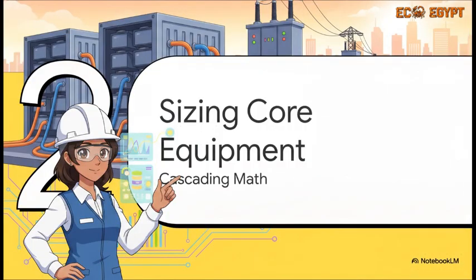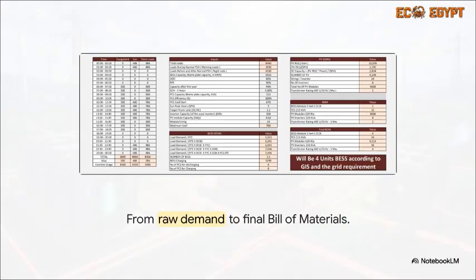Moving right along to section 2, sizing the core equipment. Okay, so where does the real math actually start? It starts with the grid's minimum energy requirement. For this specific project, the grid study demands exactly 20 megawatts of active power for a 45-minute discharge duration. Do the math, and that calculates out to 15 megawatt hours. But engineers can't just stop there. We have to factor in the real world. A 90% round-trip efficiency penalty, a 90% depth of discharge limit. Once you push that raw grid demand through all those real-world efficiency penalties and add a buffer for the battery degrading as it ages, you finally arrive at the true anchor of the project, a 20 megawatt-hour lithium iron phosphate, or LFP, battery capacity.